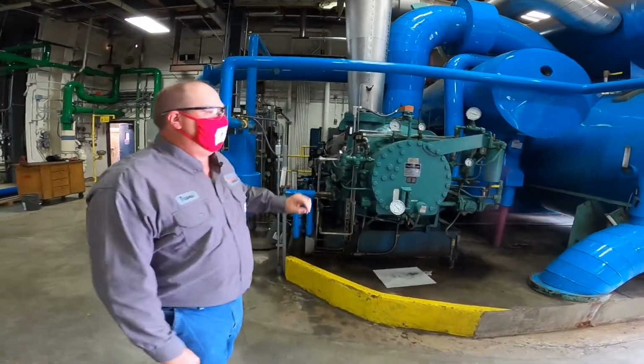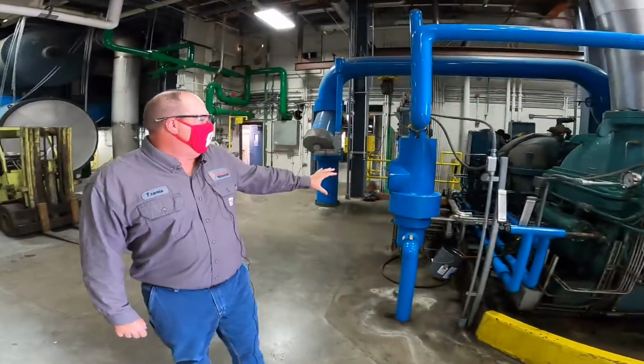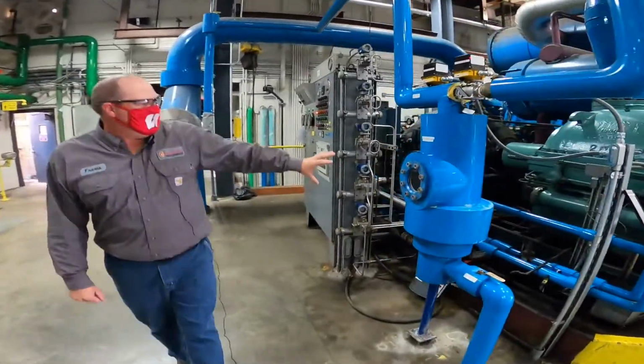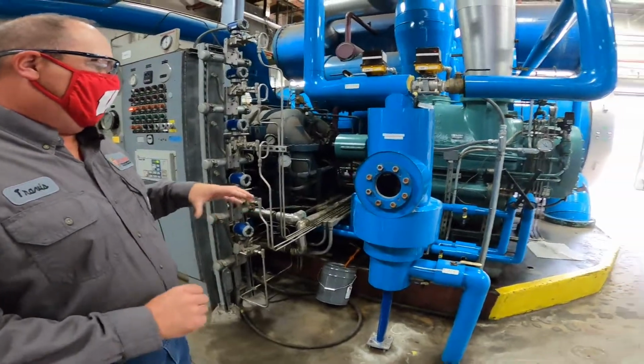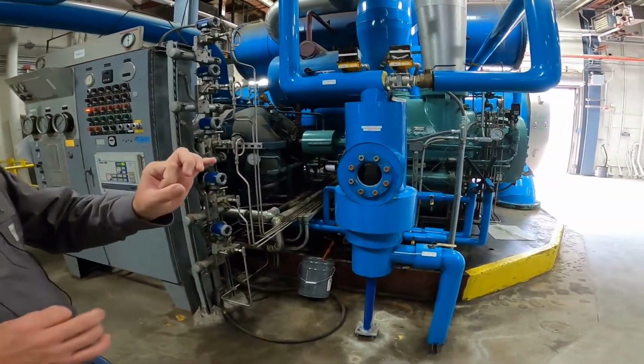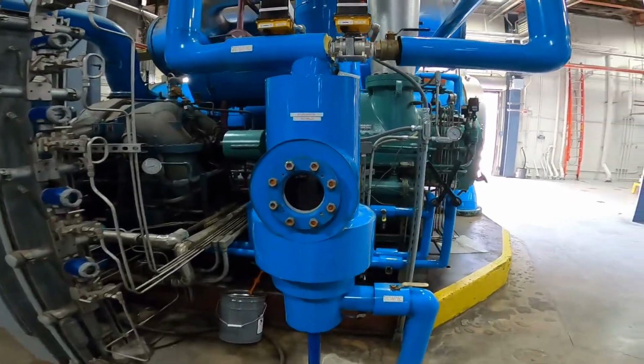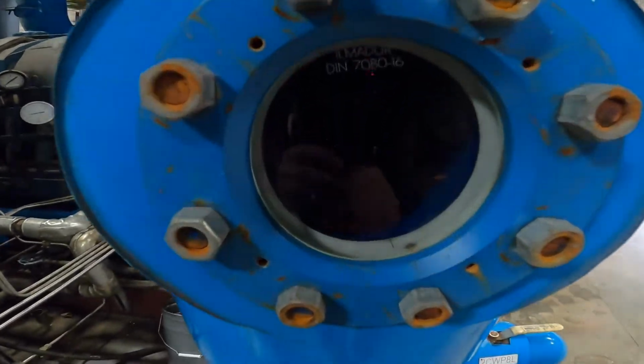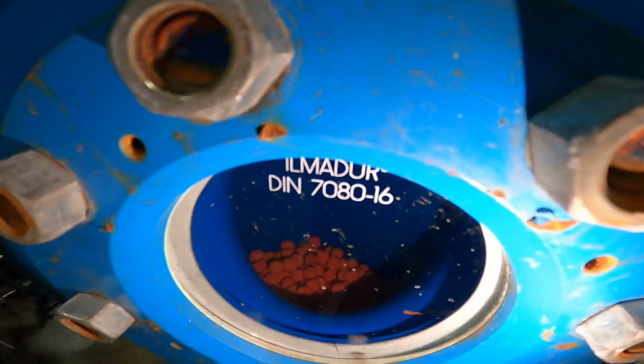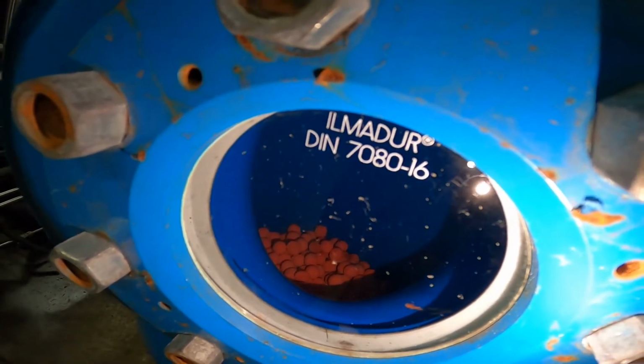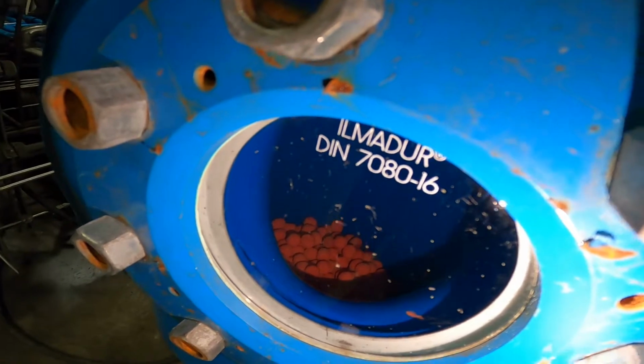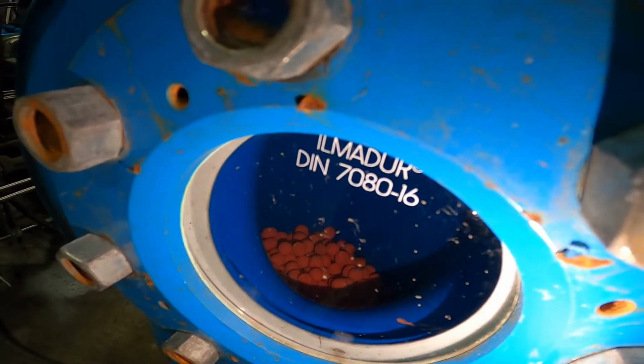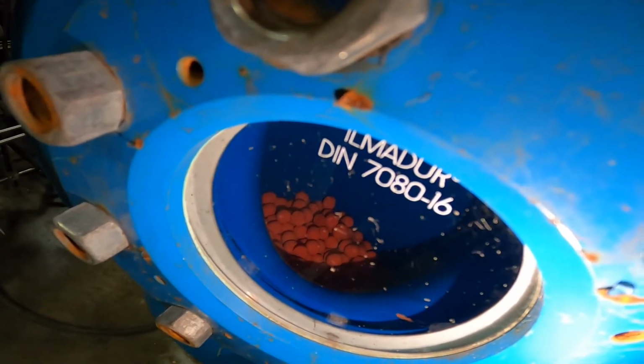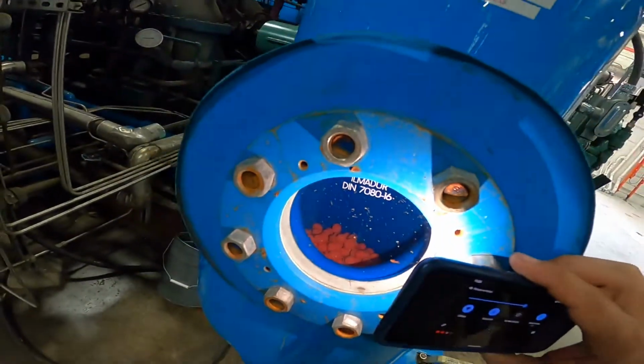So we did this little experiment here a couple summers ago. You can see this, what we call a little minion, I guess. It's just a ball system. There's little Nerf balls about 5/8 inch in diameter. There's 400 balls in this system right here, in this evaporator. And it's designed so that every 20 minutes when this system is running, when the water is actually passing through the heat exchanger, these balls get pumped through the tubes. Now you've got 3,000 tubes in that heat exchanger, and every 20 minutes the 400 balls pass through those tubes and wipe the tubes clean.